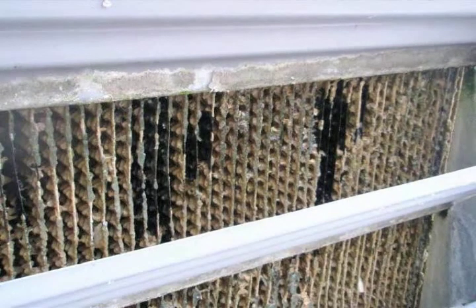Obviously, with all the technology we have, we're still seeing way too much scale formation in cooling towers. Here's an example of a plant I visited a couple weeks ago. It's a high hardness area of the country, and they just didn't take a look at their water treatment the way they should. They basically scaled up their entire fill right there. Once you scale up a system, it can be cleaned. It's painful, very painful, because the only way to really remove scale is by dropping the pH, which puts the tower system somewhat at risk from a corrosion standpoint. So there are ways to do it, but the best way is don't let it happen in the first place.